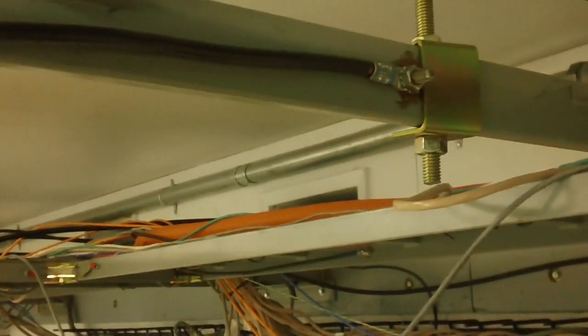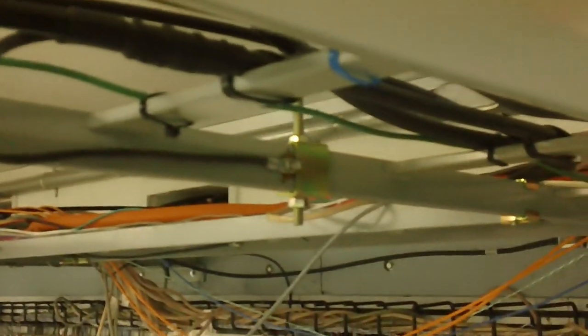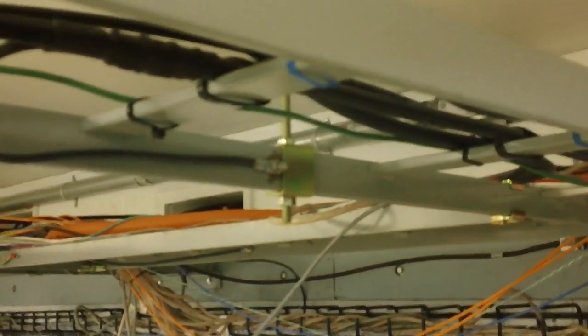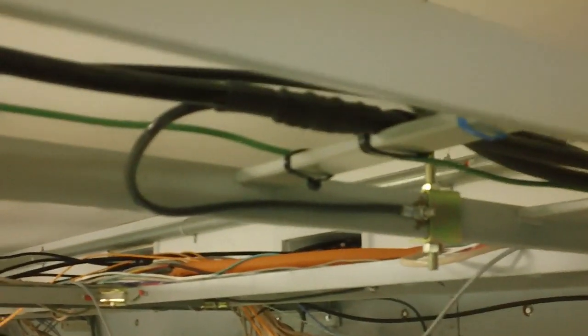Everything sits on top, and here you see the ground connected and bonded to the cable tray itself. Each section of the cable tray is bonded together with ground, which prevents danger from a lightning strike, but also helps negate radio interference, since in this room many frequencies are produced that mix and cause other frequencies — it's a big mess. All this grounding is just to negate that problem.